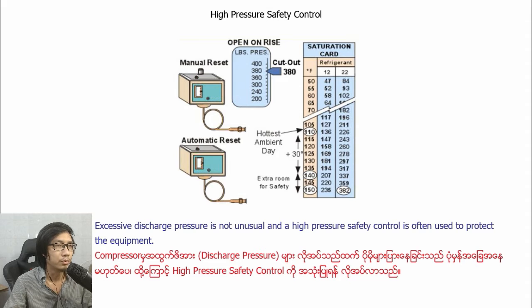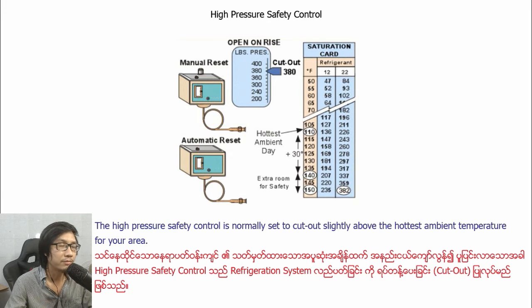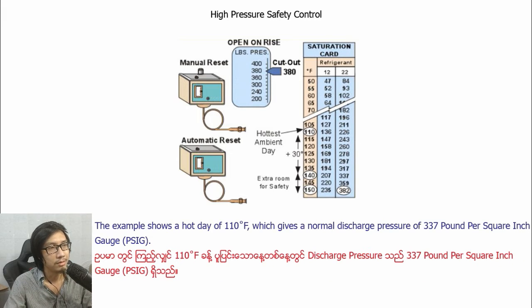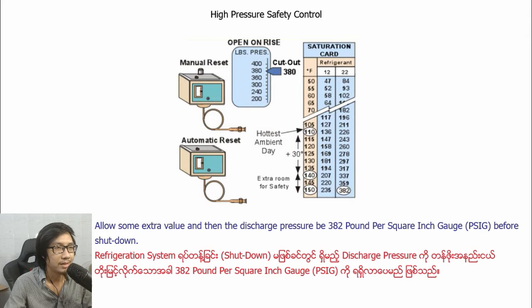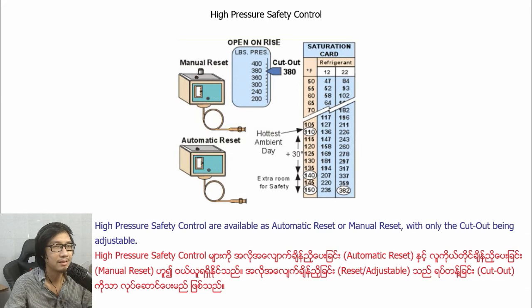High pressure safety control. Excessive discharge pressure is not unusual, and a high pressure safety control is often used to protect the equipment. The high pressure safety control is normally set to cut off slightly above the hottest ambient temperature for your area. The example shows a hot day of 110 degrees Fahrenheit, which gives a normal discharge pressure of 337 PSIG. Allow some extra value, and the discharge pressure can be 382 PSIG before shutdown. High pressure safety controls are available as automatic reset or manual reset, with only the cutoff being adjustable.